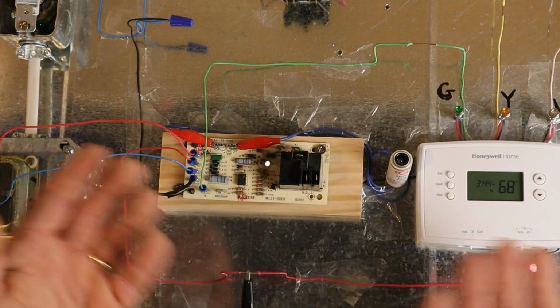Now as you can see, absolutely nothing happened. If your guess was that this was going to create a short, don't feel so bad. A lot of people would have guessed that. Let's begin by showing you why this didn't create a short circuit and what I do first before I do anything else, that sometimes can actually help me narrow the problem down to either one or two components. In the worst case scenario, it actually tells me what I should be looking for when I begin my testing.